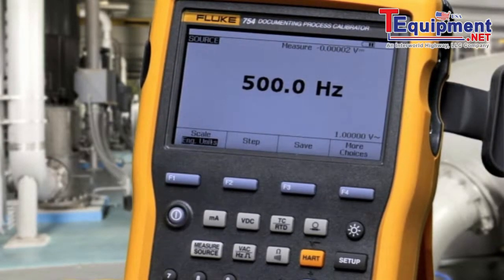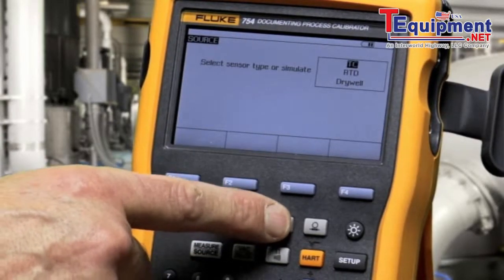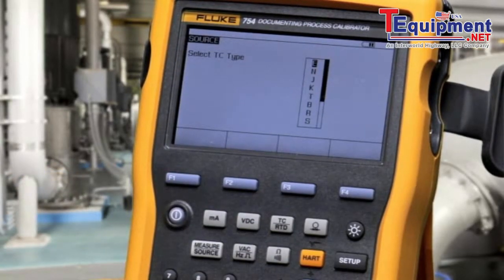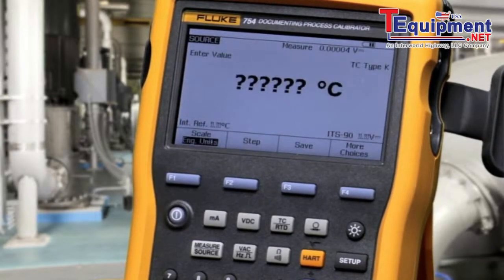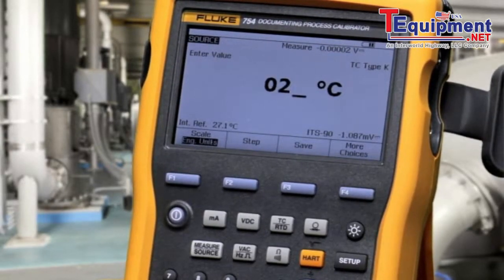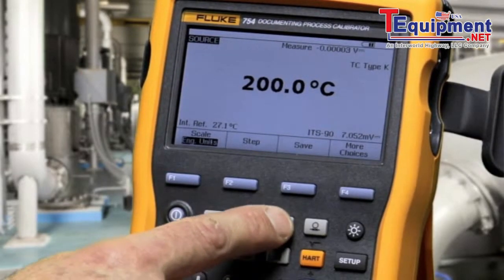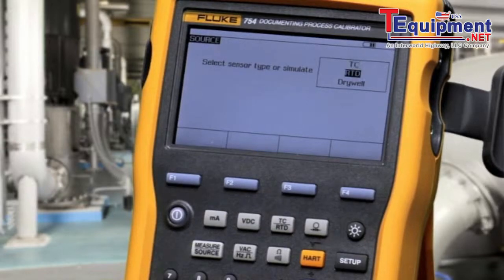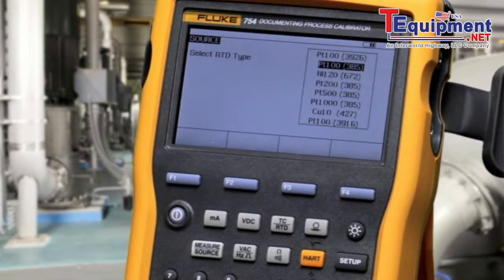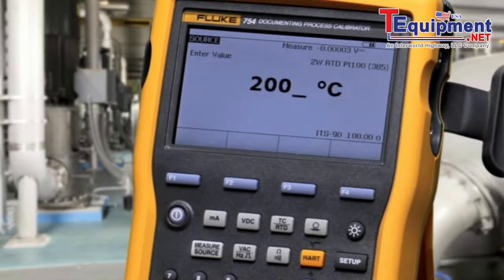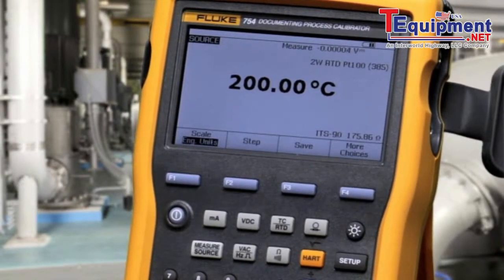To source temperature, select thermocouple or RTD. For thermocouple, make your connection on the mini connector, select your function, and type in the value you want to source. To source an RTD, select RTD, select your RTD type, type the value you want to source, make your connection, and apply that temperature value to the device you're testing.